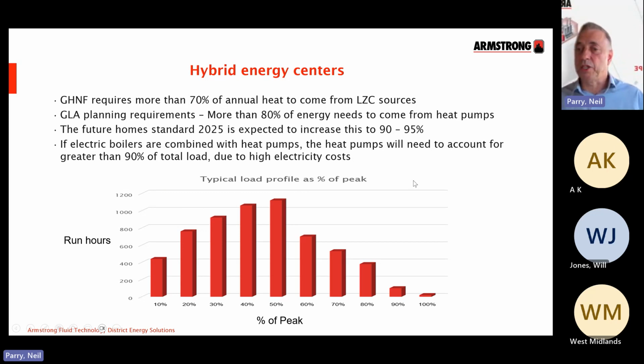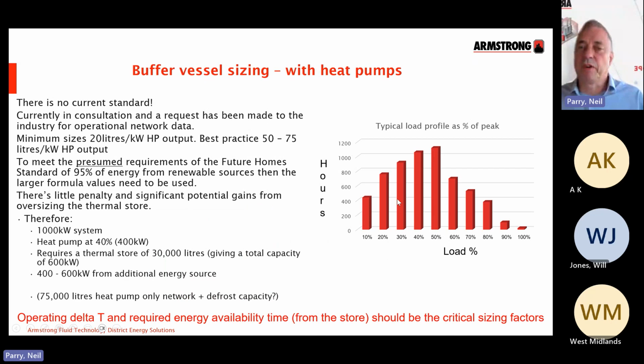Now, that obviously has implications. So when we say we need 95% of our energy to come from a low to zero carbon source, that doesn't mean that we need to have heat pumps sized at 95% of peak. Far, far from it. And what we typically see here, and I've pulled some data from various different sources here, is that we can look at using a heat pump of around 40% of peak, and if we integrate thermal storage with the renewable energy source, that will typically give you your 90 to 95% of energy coming from a low to zero carbon source.